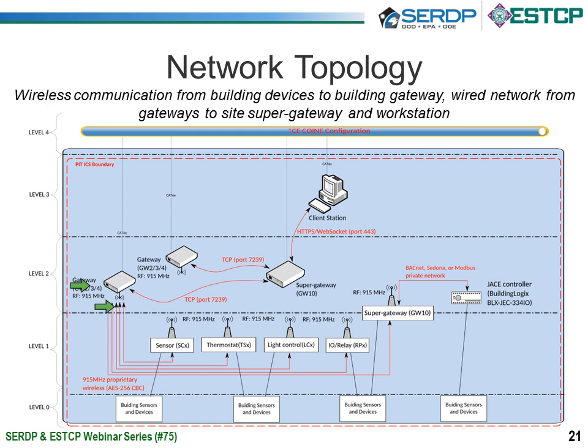Each of these gateways then sets up a local wireless network within the building or within an area of the building, and can communicate to hundreds or thousands of different wireless sensors shown here in level 1. These gateways at level 2 then communicate with other gateways at other buildings, and then also to a super gateway, which is kind of like a mini server at the facility that handles authentication and other high-level requirements. And then the users on site communicate with this entire system through a DoD imaged workstation, and using a browser-based interface can communicate and access the entire system.